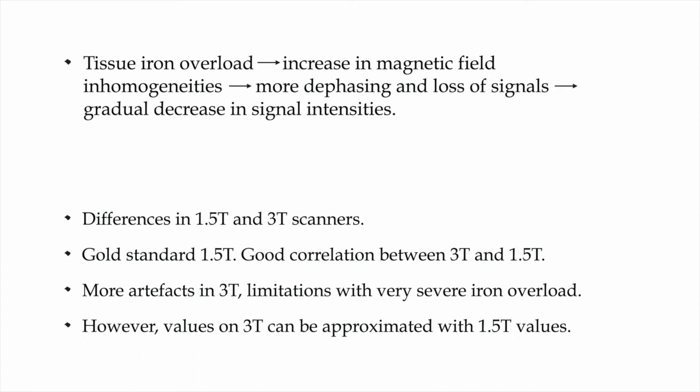Regarding whether to use a 1.5T or 3T scanner: 1.5 Tesla is the gold standard for iron quantification by MRI. However, there is a very good correlation between 3T and 1.5T values. In patients with very severe iron overload, there are more artifacts in the myocardium on 3 Tesla images, and quantification may yield only limited values. So the first preference for iron overload assessment is a 1.5 Tesla machine, though 3T machines are also good and their values correlate well with 1.5T.